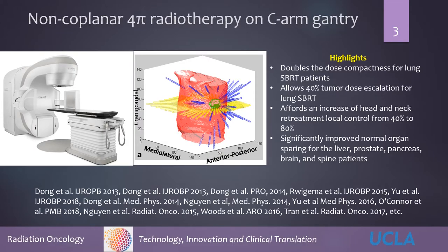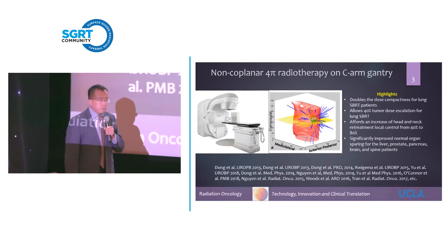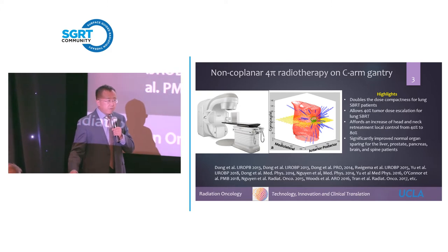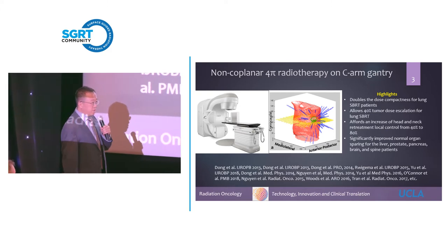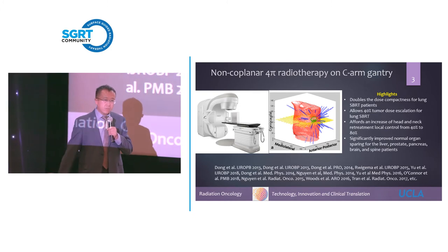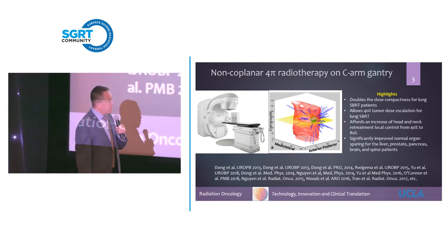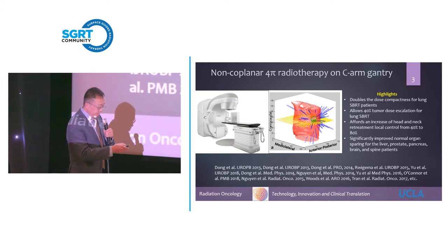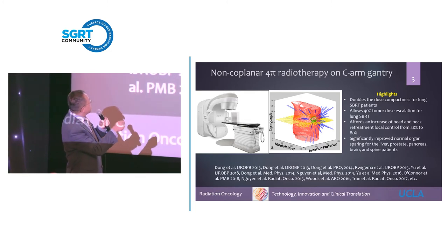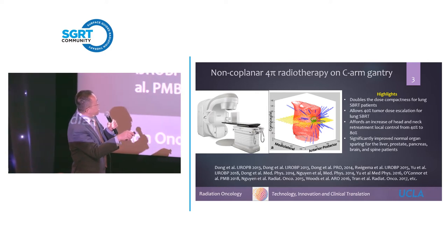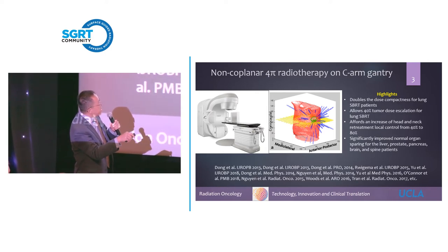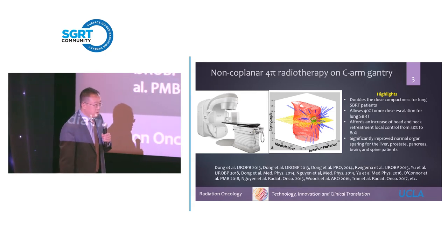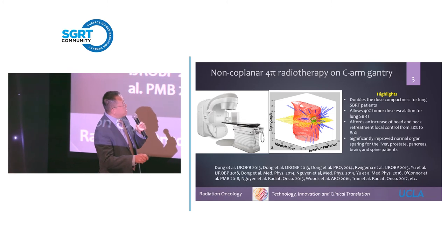This is what we have been doing extensively in the past seven years, which is inverse optimization — extensively using non-coplanar angles to create the best possible dose distribution for some of the complex and challenging cases. Using the C-arm gantry system, instead of conventional coplanar beams, we use many non-coplanar beams to treat the tumor. We've published close to 30 papers on this topic.